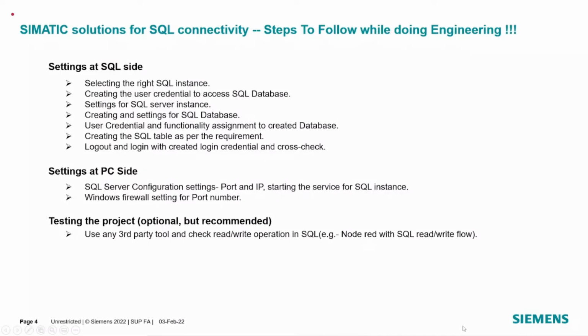So at the SQL side, what will be required? You have to select the right SQL instance, because you know that on some PC, you may have SQL Express installed, or SQL Server installed. So whenever you are declaring or defining where you want the data to be logged in, or read or written from, you have to select the right instance. Further, whichever instance you are selecting, all the settings related to that instance have to be followed in all the areas, including the PLC side, PC side, everywhere.